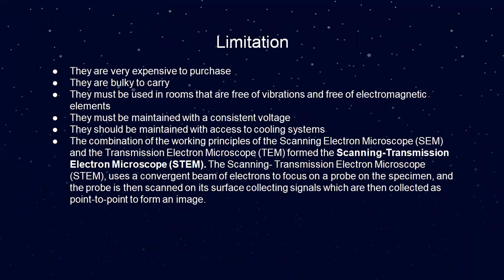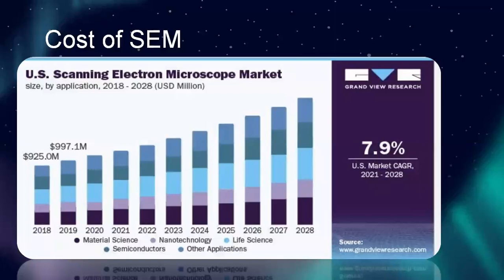Limitations of the scanning electron microscope: they are very expensive to purchase. They are bulky to carry. They must be used in rooms that are free of vibration and free of electromagnetic elements. They must be maintained with a consistent voltage. They should be maintained with access to cooling systems. And lastly, the combination of the working principles of the scanning electron microscope and the transmission electron microscope forms the scanning transmission electron microscope, which uses a convergent beam of electrons focused as a probe on the specimen; the probe is scanned on its surface collecting signals which are collected as point-to-point format images. The cost of the scanning electron microscope has been tracked from 2018 through 2023 and onwards.